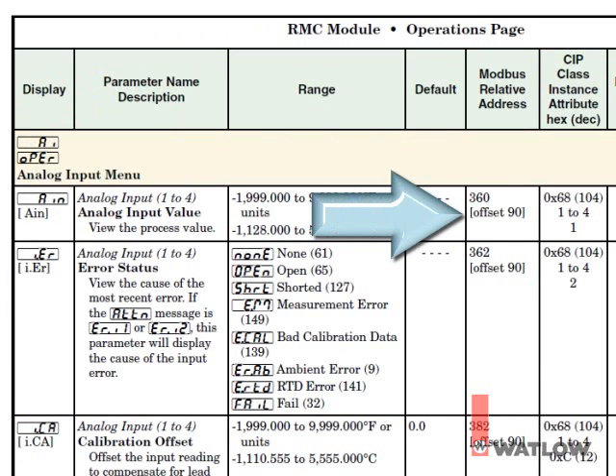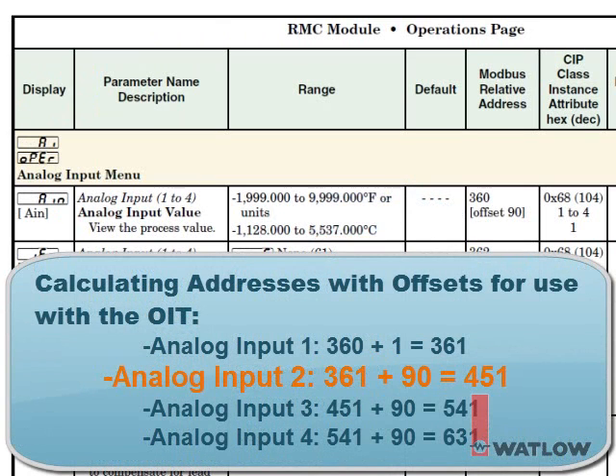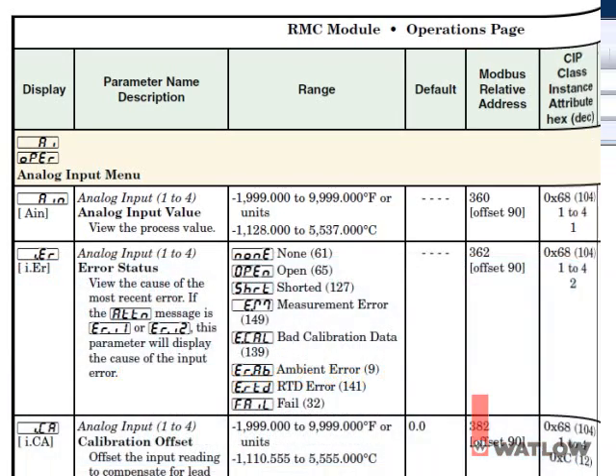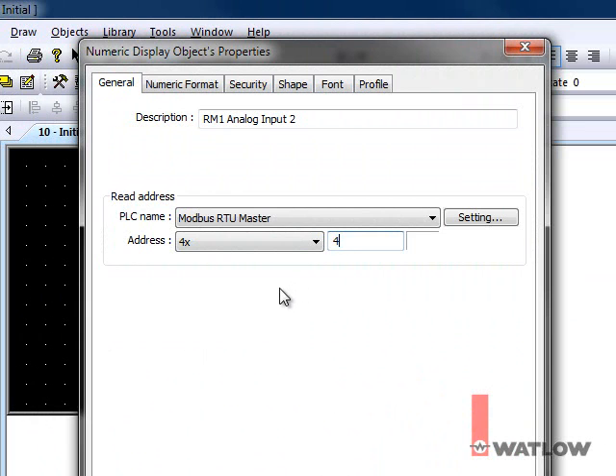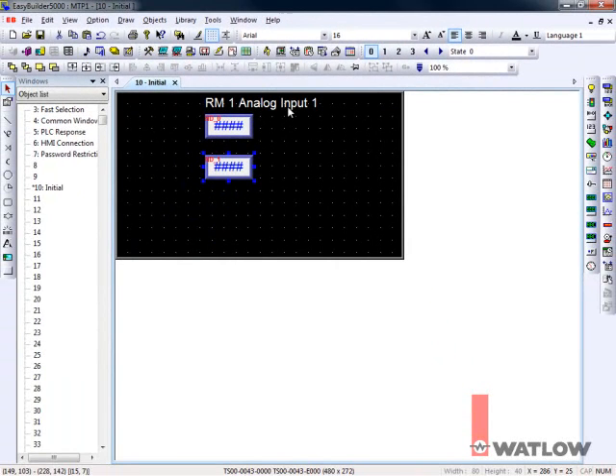Note that for each Modbus address in the manual, an offset is also included. That offset is used to determine the addresses for the other instances of the parameter in the same controller, in this case for the other analog inputs. The instance offset listed for analog input value is 90, so the address for the second analog input's value is 361 plus 90, 451. And the address for the third analog input's value would be 451 plus 90, 541, and so on. So for the second input, enter the address 451. That's 360 plus the offset of 90 plus 1 to use it with the OIT.